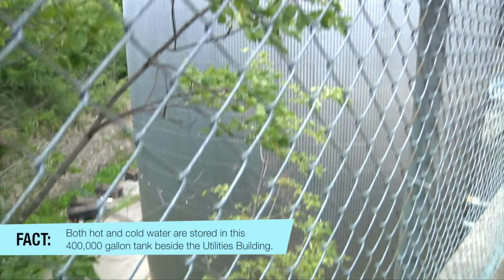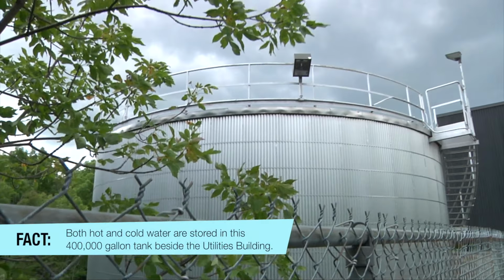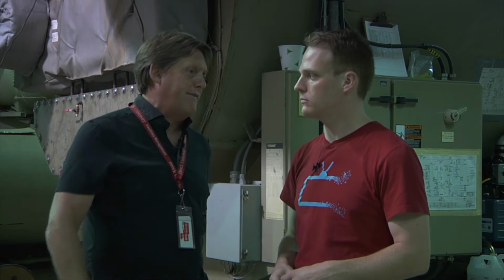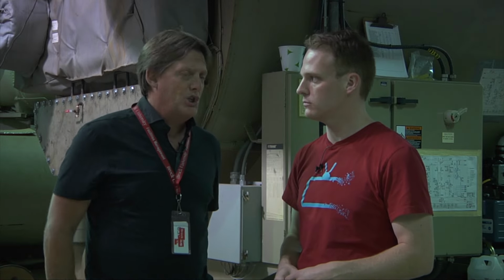In the summertime, we'll run the chiller through the night and cool down 400,000 gallons of water. Around 1 o'clock in the afternoon, we'll add that water to the system, which adds effectively about 200 tons of chilling.